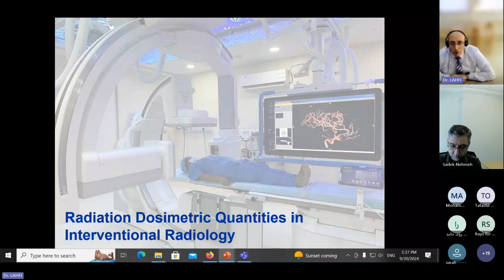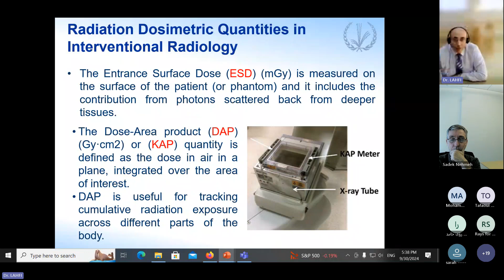The first one is the entrance surface dose, ESD, which is measured in milligray and is measured on the surface of the patient or phantom, and it includes a contribution from photons scattered back from deeper tissue. The second quantity is the dose area product, or Kerma area product, which is defined as the dose in air in a plane integrated over the area of interest. This quantity is useful for tracking cumulative radiation exposure across different parts of the body.